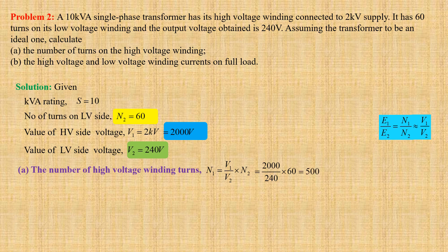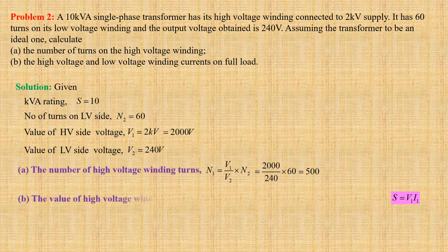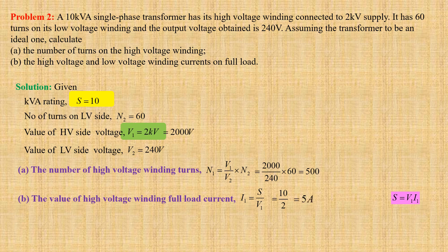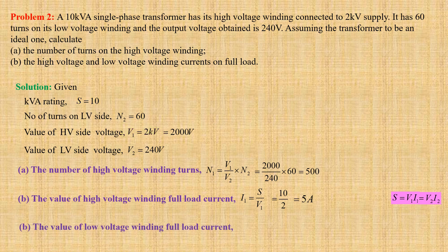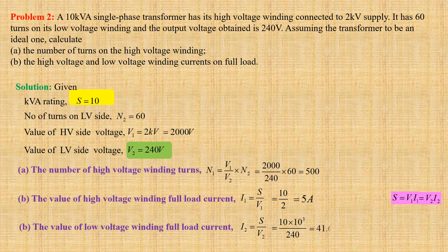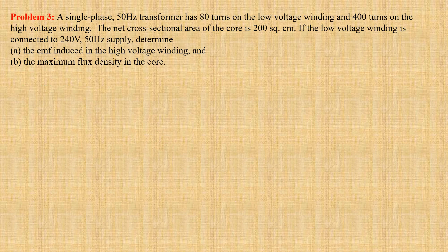For a single phase transformer, S equals V1 × I1. The high voltage winding full load current I1 equals S/V1, that is 10 × 10³ divided by 2000, which gives us 5 ampere. For a single phase transformer S equals V2 × I2. The low voltage winding full load current I2 equals S/V2, that is 10 × 10³ divided by 240, which gives us 41.67 ampere.